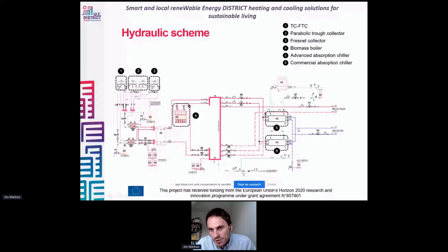On the secondary side, there are three circuits. One is the district heating network, the third one, that connects to the CEPSA building, and the other two circuits feed the cooling technologies. There are two chillers in the power plant: one is the high efficiency absorption chiller, and the other is a commercial chiller. The chilled water circuits from both chillers merge into one cold water circuit, which is the district cooling that connects to the CEPSA building.